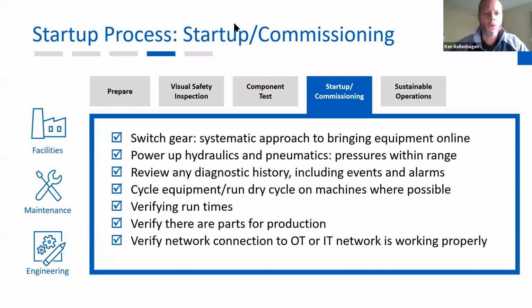All right, so after that component test is done, thorough inspection of looking at all things, we're going to start up that actual commissioning process, running cycles, things like that. So with switchgear on the facility side, we really need to take bringing things back online as your whole building system in a very strategic approach. Shutting downstream loads off first before we engage that main, just saving on wear and tear, both on a safety and just from that hardware aspect, saving the wear and tear on that equipment.